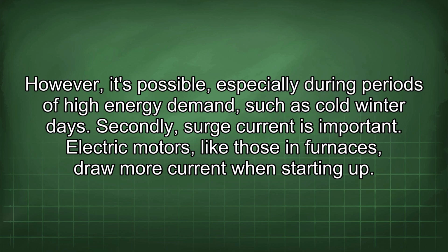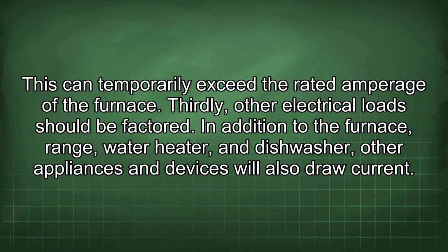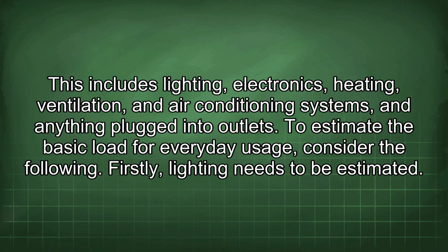Secondly, surge current is important. Electric motors, like those in furnaces, draw more current when starting up. This can temporarily exceed the rated amperage of the furnace. Thirdly, other electrical loads should be factored. In addition to the furnace, range, water heater, and dishwasher, other appliances and devices will also draw current. This includes lighting, electronics, heating, ventilation, and air conditioning systems, and anything plugged into outlets.